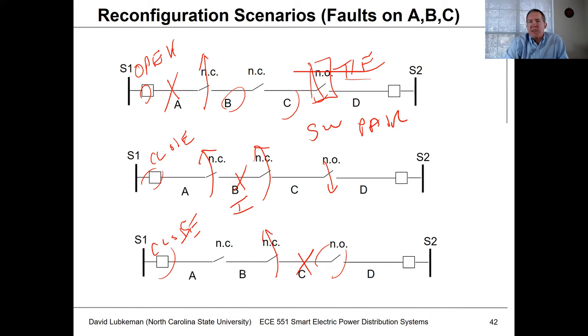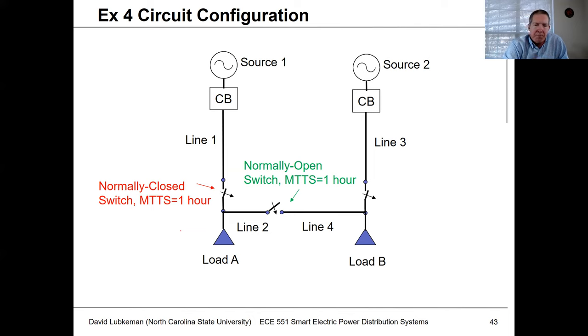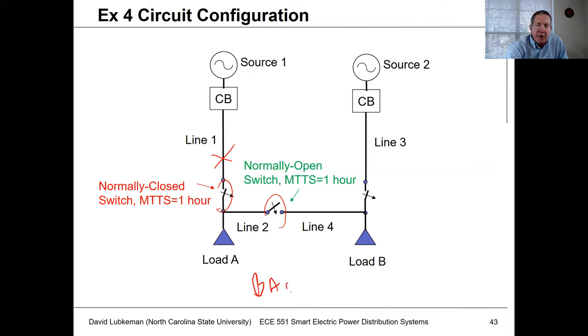If the time to do the switching is less than the time to repair, it's worthwhile to send a crew out there to do circuit reconfiguration first before fixing the fault. This is the scenario we're going to look at. Since it's a new scenario, we have to redo the base case. Basically, what we're looking for is a way where if I have a fault on line one, I open this switch and close this switch — what we refer to as a back-feed scenario.